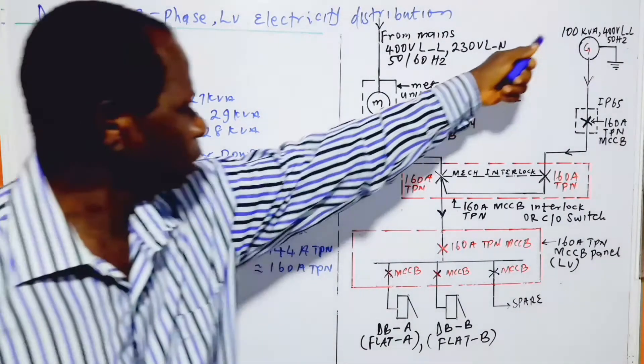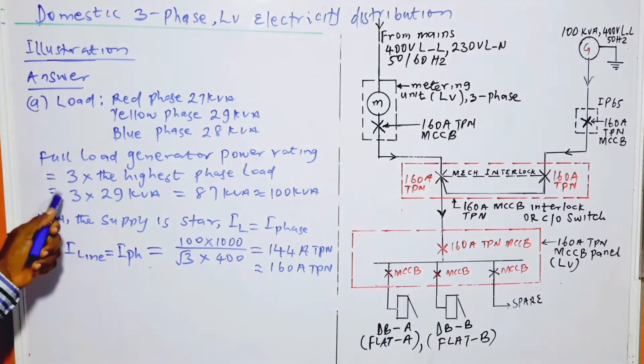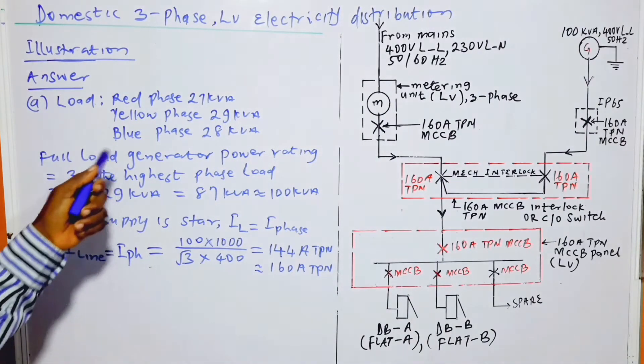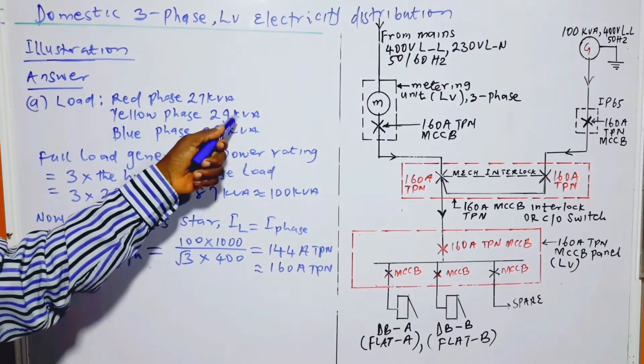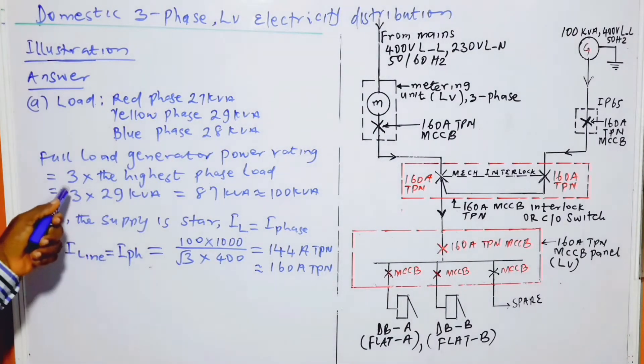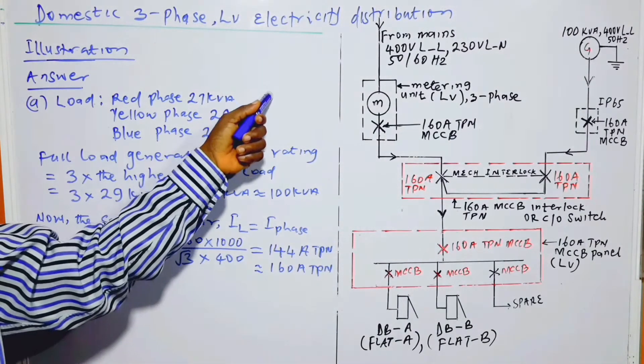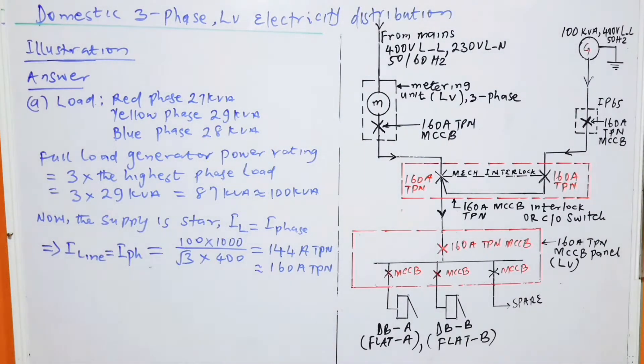You have to multiply the highest phase load, which is 29, by 3. If you take the algebraic sum of the phase loads, it will be incorrect, just as I explained in one of my videos regarding the sizing of transformers.